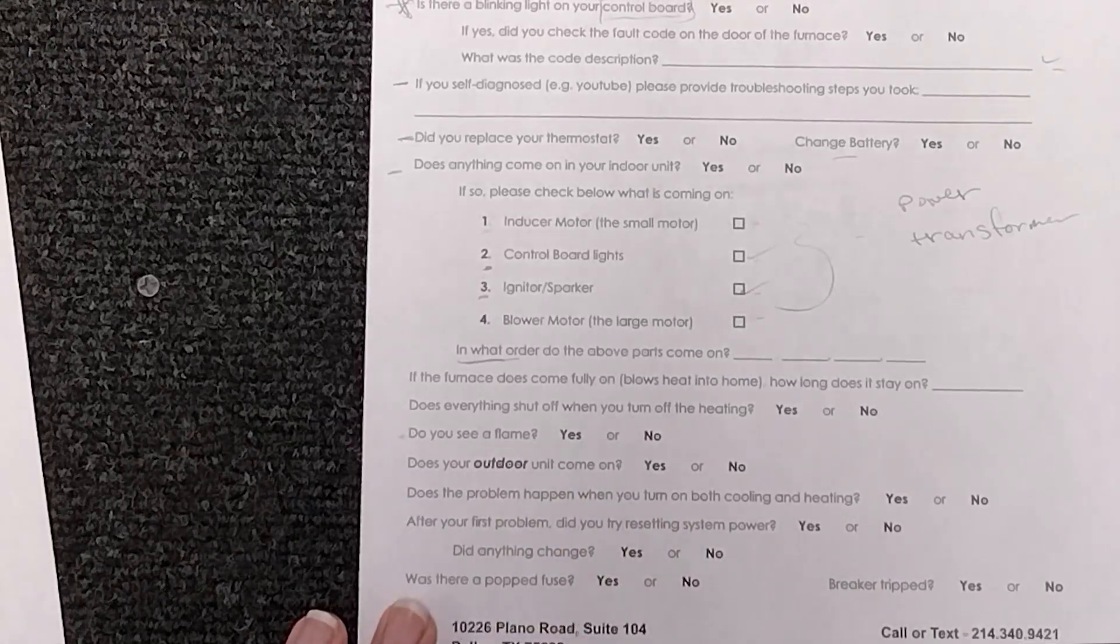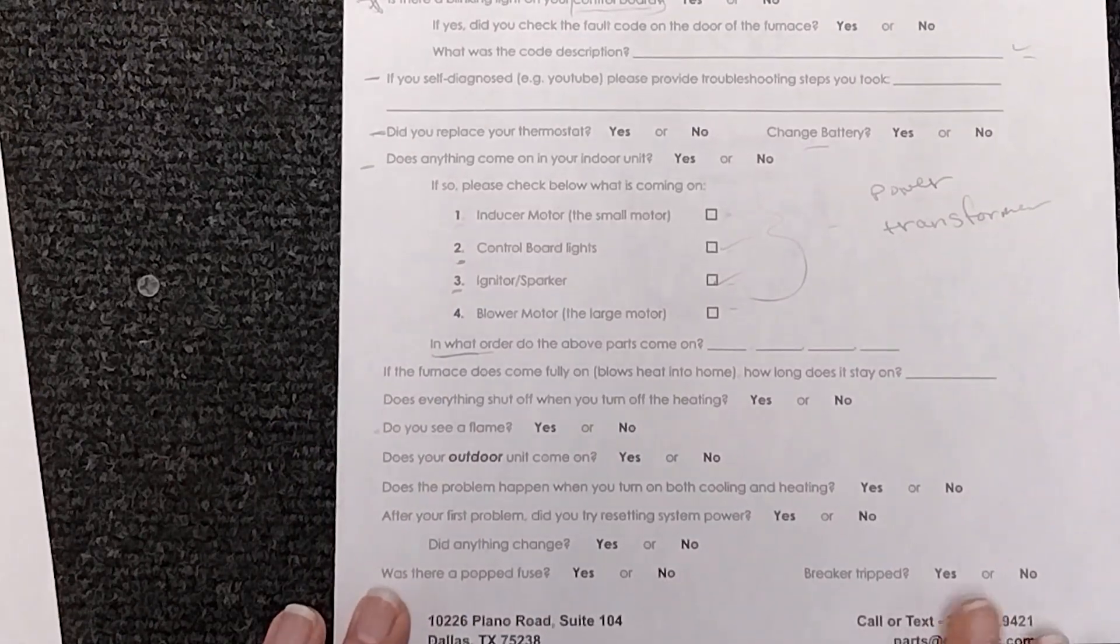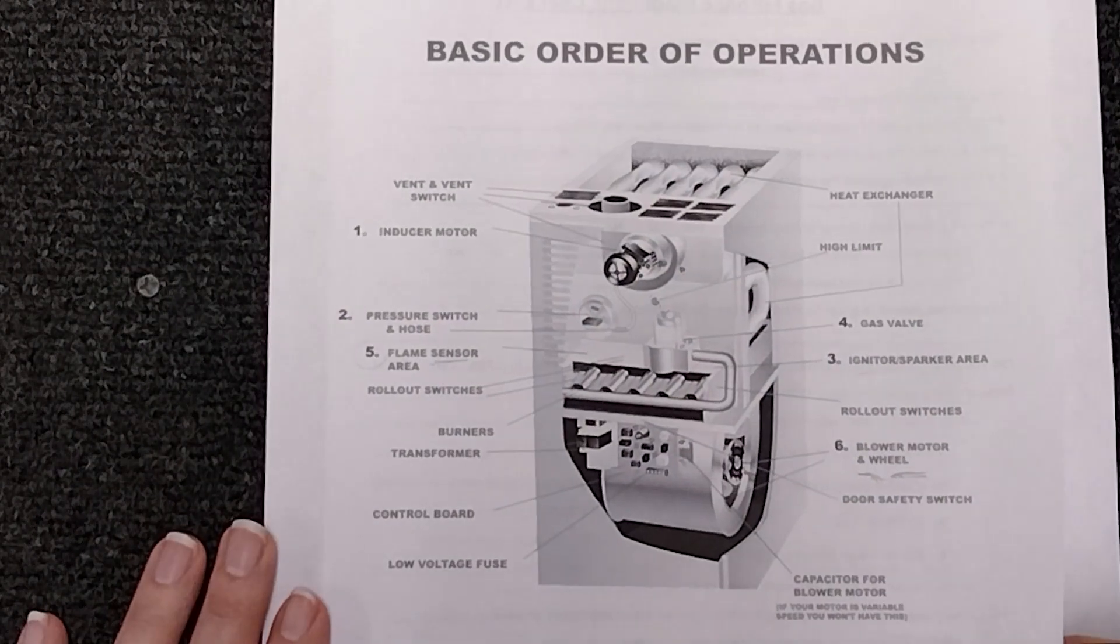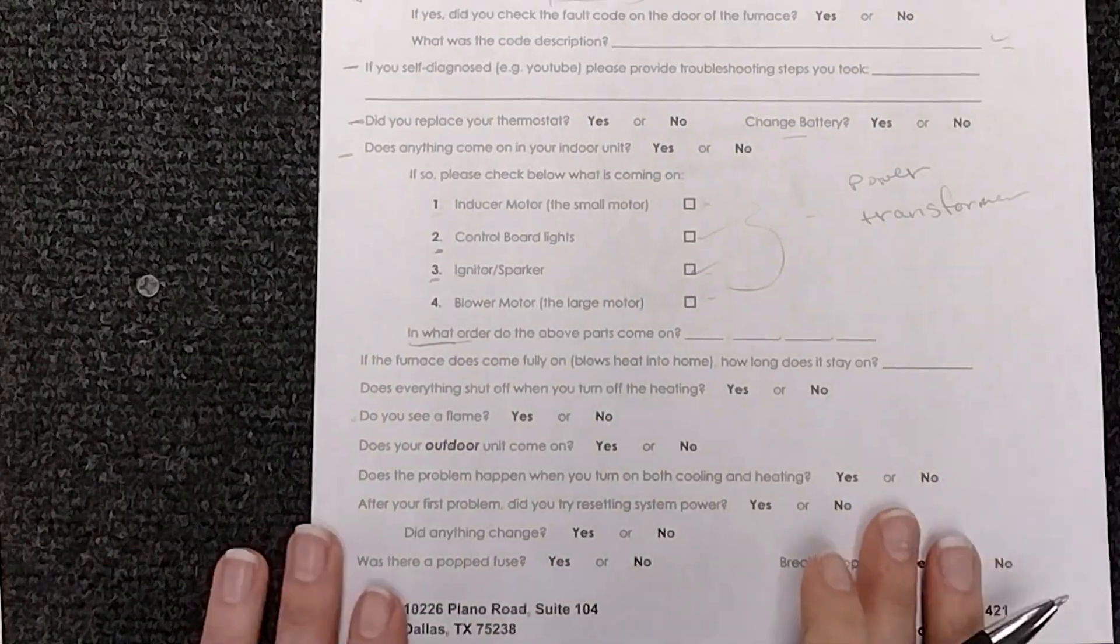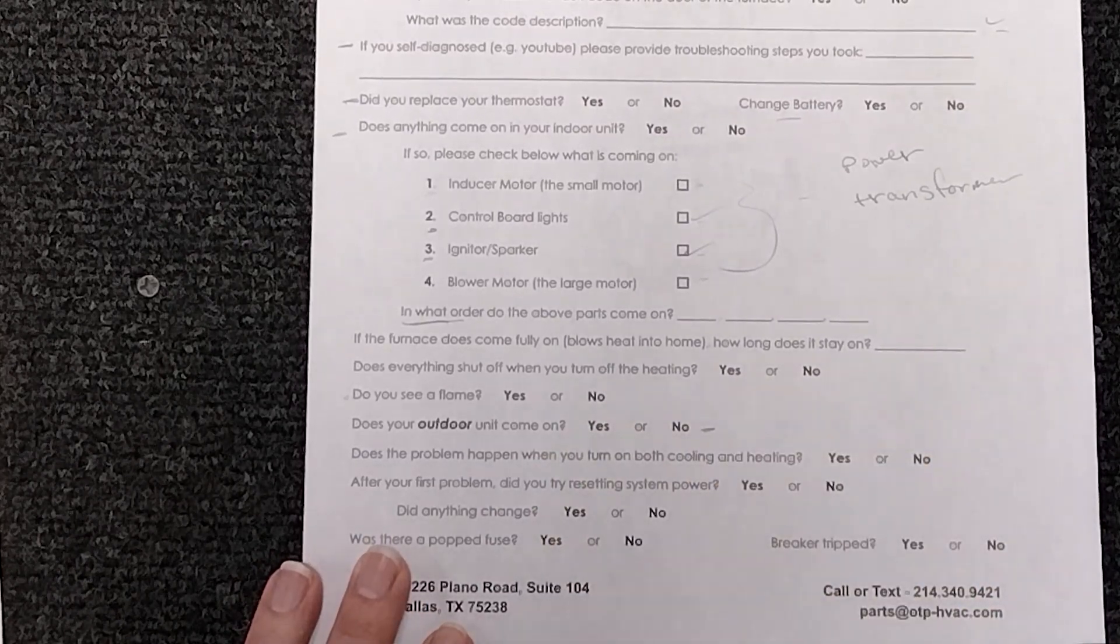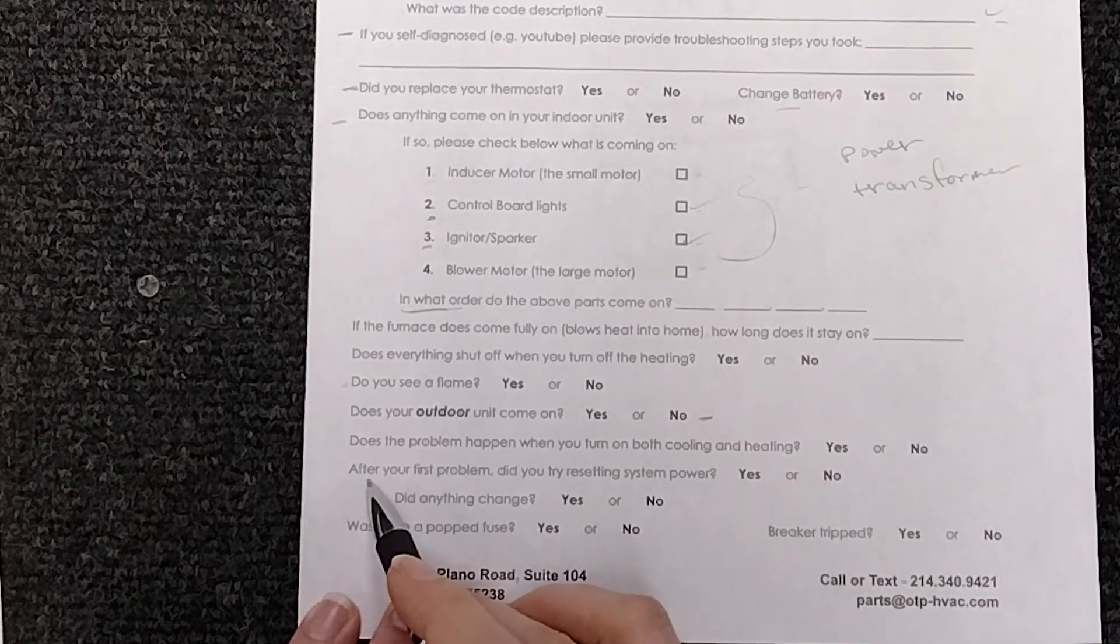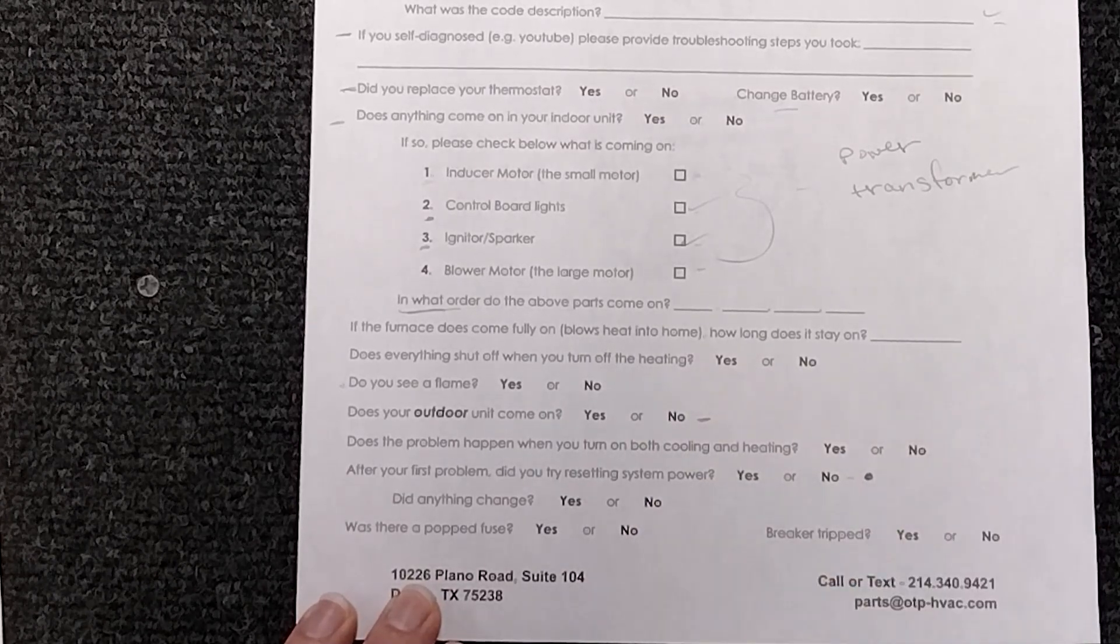Does your furnace light? Make sure that you're actually seeing a flame because if you're not seeing a flame a flame sensor is not going to be your problem. So does your igniter glow etc. It all goes back to our rule of basics here. So save yourself the problem. Really look at this. As I've said before does your outdoor unit come on? Check your cooling. Make sure that's happening.